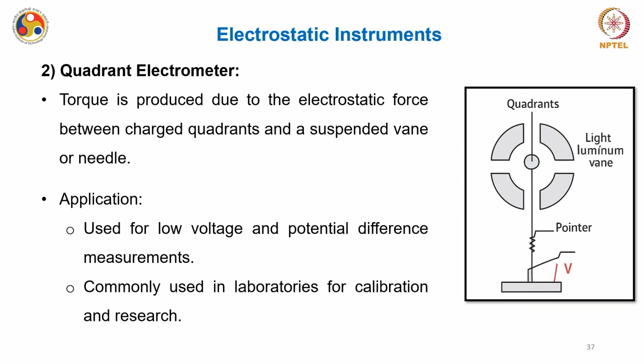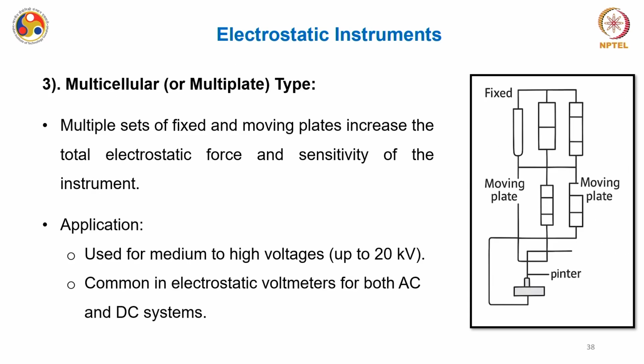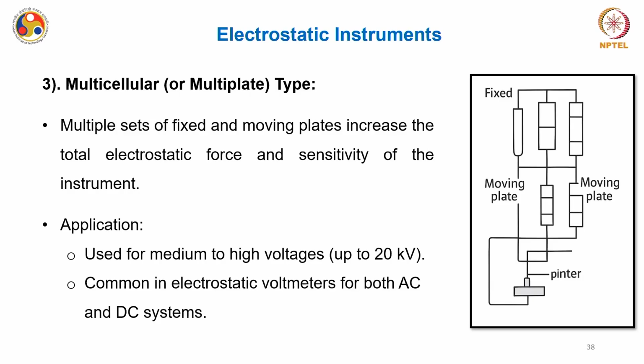The second kind of instrument is the quadrant electrometer, where the torque is produced due to the electrostatic force between charged quadrants rather than the spheres or discs. You have different quadrants, you can see this, and a suspended vane or a needle. They are used for low voltage and low potential difference measurement, and they are very common for calibration purposes. Then you have the multicellular or multiplate type of instrument. As the name suggests, they have multiple sets of fixed and moving plates, which increases the total electrostatic forces and the sensitivity of the instrument. They are usually avoided for measurement of low voltages, and are used mostly for medium and high voltage measurements, and they are common in electrostatic voltmeters for both AC and DC measurements.